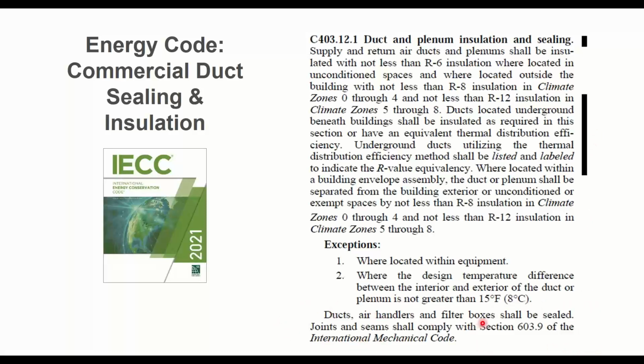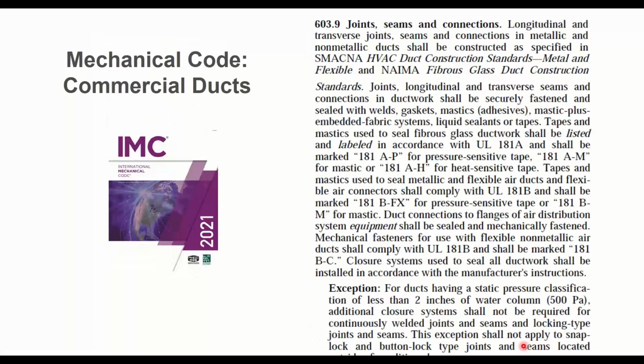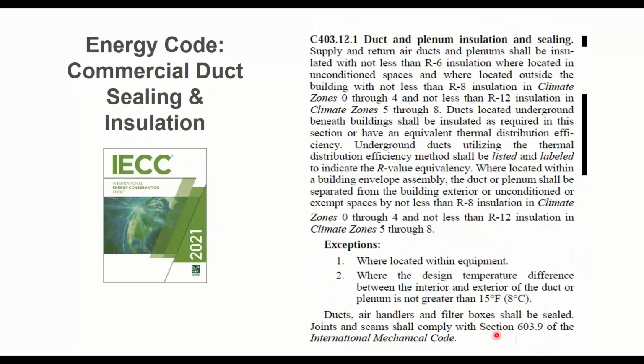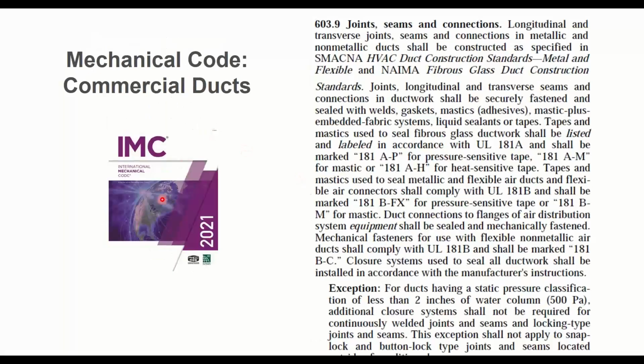Ducts, air handlers, and filter boxes shall be sealed. Joints and seams shall comply with the IMC, International Mechanical Code. So the energy code is telling you you have to seal these things up. They're not telling you how to do it or what level of sealing. They're directing you over to another book that you must acquire and put into your library. That mechanical code book looks like this. This is the section specifically related to joints, seams, and connections, right? So this reference down here drove me over to this particular book.